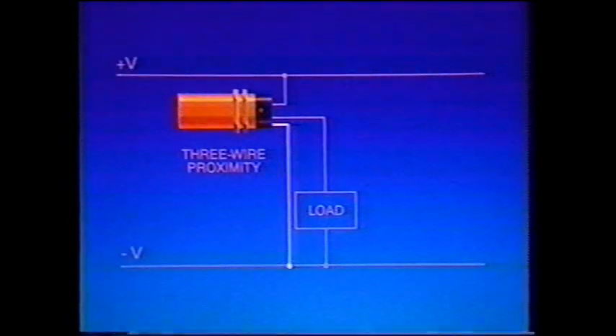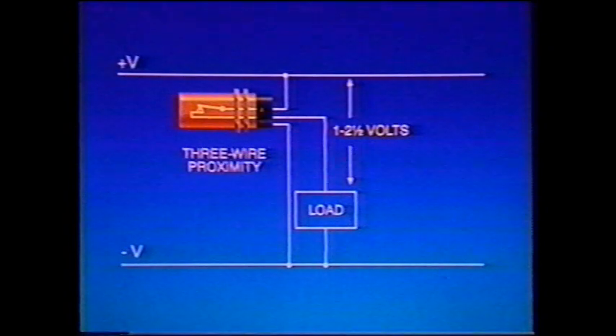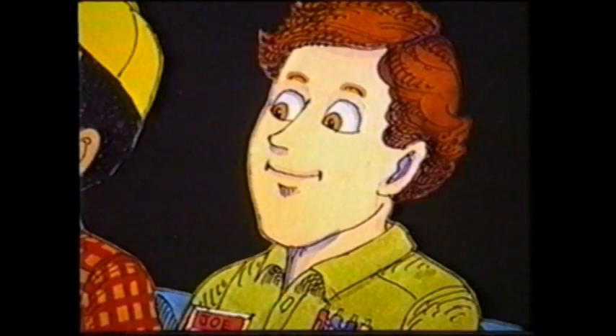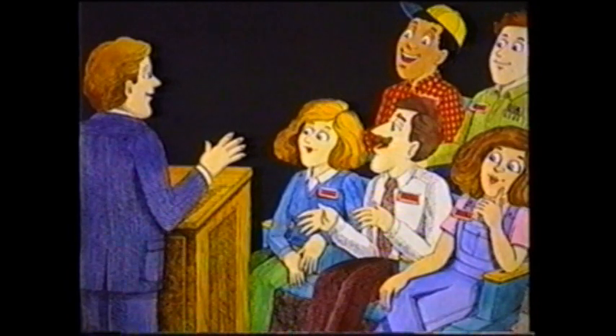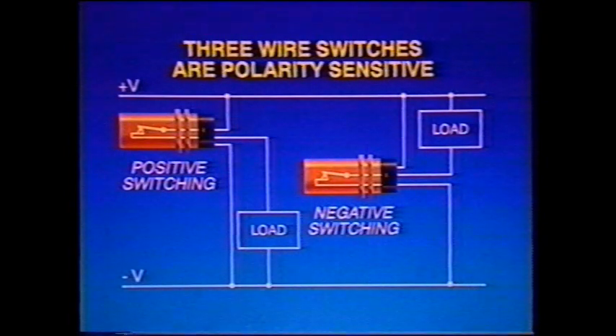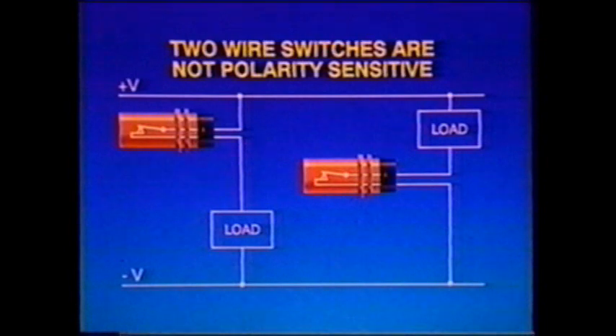A three-wire proximity switch is different because energy for the switch is supplied through a third wire. When the three-wire switch is closed, it has a smaller voltage drop — usually one to two and a half volts — and when it is open, the three-wire switch has essentially zero leakage current. Two-wire switches have many advantages: because there is one less wire to connect, two-wire switches cost less to install. Three-wire switches are polarity sensitive — you must specify and stock separate switches for positive or negative switching applications. But two-wire switches are not polarity sensitive, so you can stock one switch and reduce the spares needed. The same switch will interface with both positive and negative switching programmable controllers.